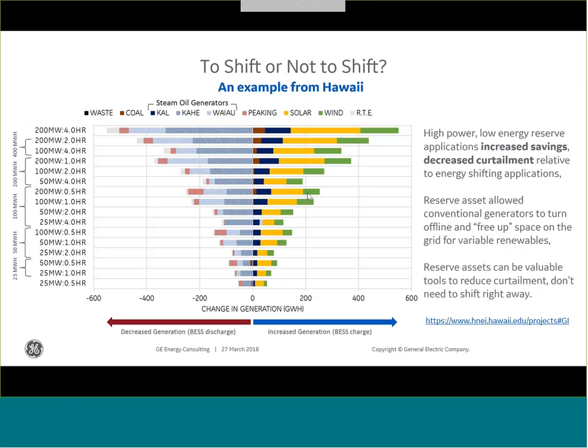Because there's less capability to shift energy from middle of the day to evening peak. What we saw was that by having a high power asset, it was able to provide reserves like regulation reserves and fast frequency response, allowing other conventional generators to go offline in the middle of the day. So not only can you shift from one time period to another, but more importantly, we're able to free up space on the grid when solar output is highest.